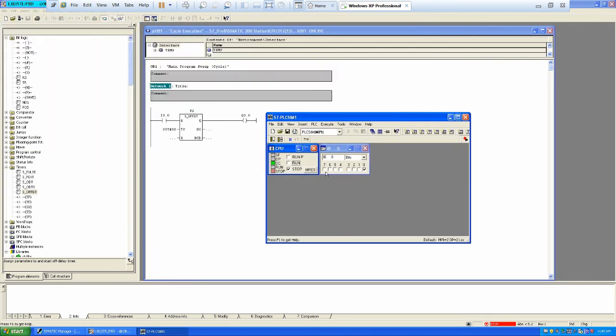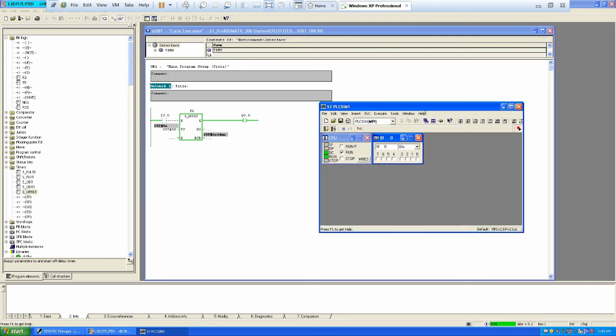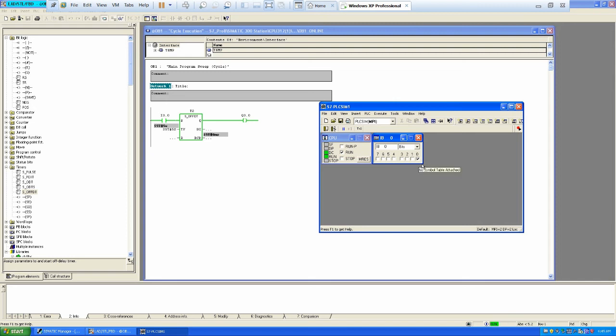And I will just try to run and watch from here. We will try to look at when I press I0.0. So we got an output. So that means when we, for example, output was high and it goes to the low condition, like due to any reason we are not able to get that input, so it will wait for 5 seconds to get the output to off. You can see here, I'm going to remove that I0.0 from here. So when I will remove it, it starts counting up. When 5 seconds will reach, it will turn off that output. But that's it about off-delay timer.